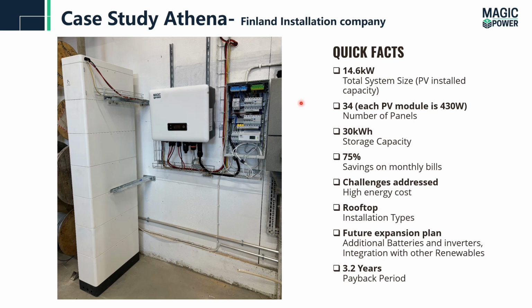So here is the case. The system installed in Finland. The system is 15 kilowatt. The energy storage is 30 kilowatt hour. The system size for the PV is 14.6, where each PV module is 430 watt. The storage capacity is 6 modules, each one is 5 kilowatt hour, so the total is 30 kilowatt hour. Cost saving on the monthly bill is up to 75%.